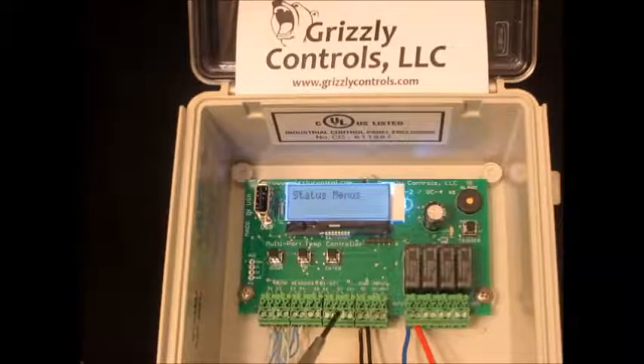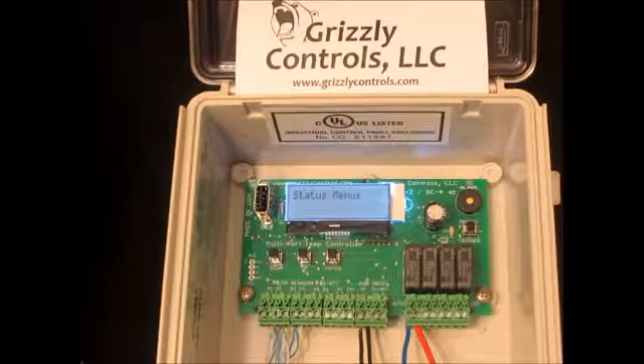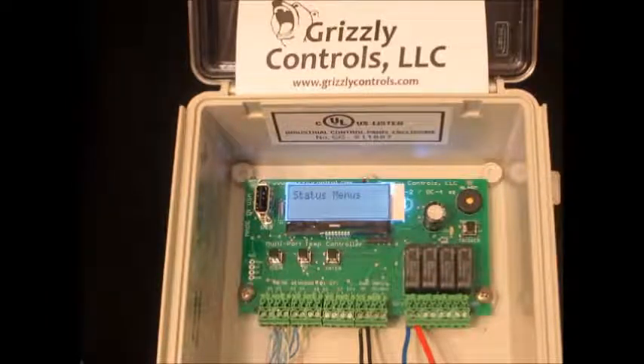It has an external powering interface that we use with the sensor adapter modules. There's a sensor adapter that lets you read whether AC or DC voltages are present. There's a sensor adapter available that will let you read analog voltages from 0 to 32 volts into the controller on any of these sensor inputs. You can then log with them or control things with them, just like if the AC is present. There's also a solar adapter sensor and an external relative humidity sensor you can bring into the unit.